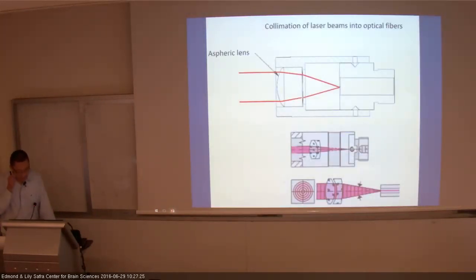Now there's one important thing: how to feed the light into the fiber, because normally the fibers that you use are relatively thin. Their core is several hundred micrometers, while regular light sources or detector sizes are several millimeters in size, and you need some kind of optics to conjugate them. This typically is done by an aspheric lens that converges light onto, this is not a theoretical point, but a certain size. And there's a certain device that does this job, so let's just call it the fiber interface.